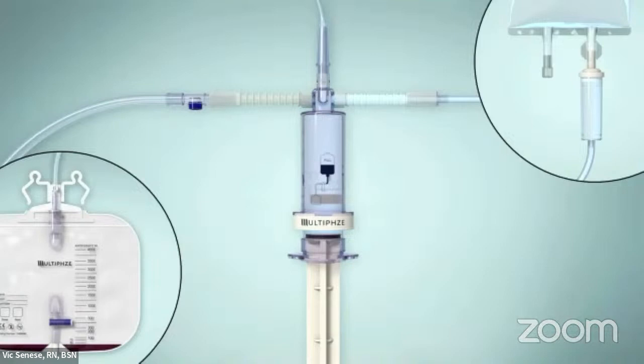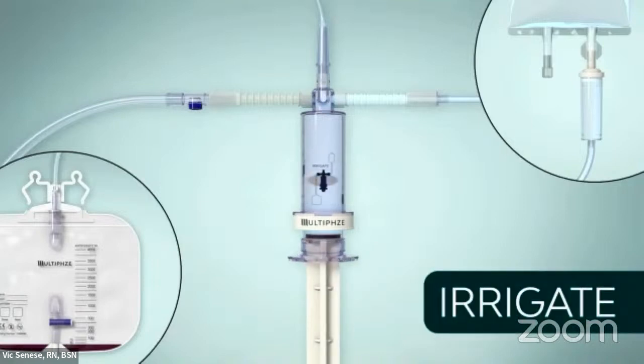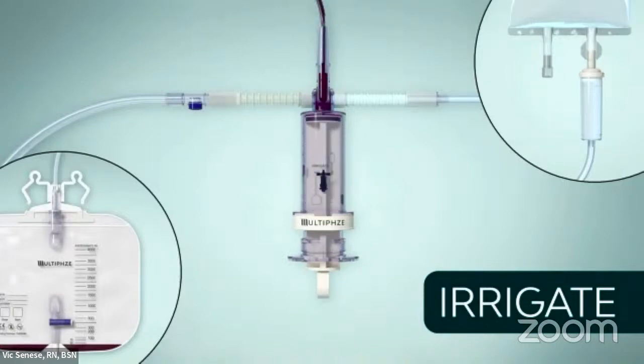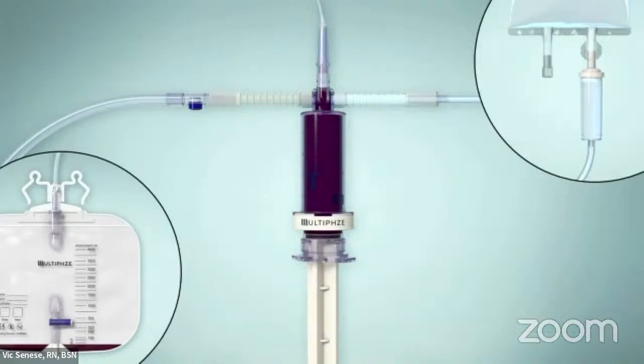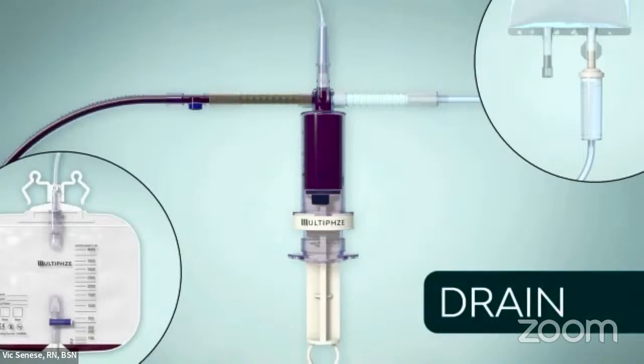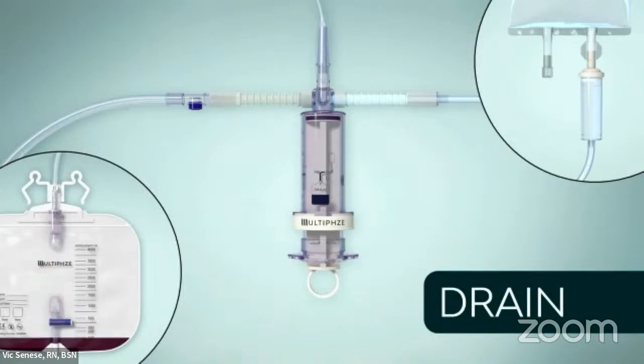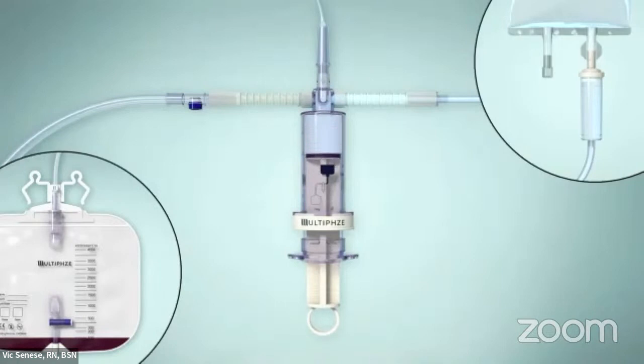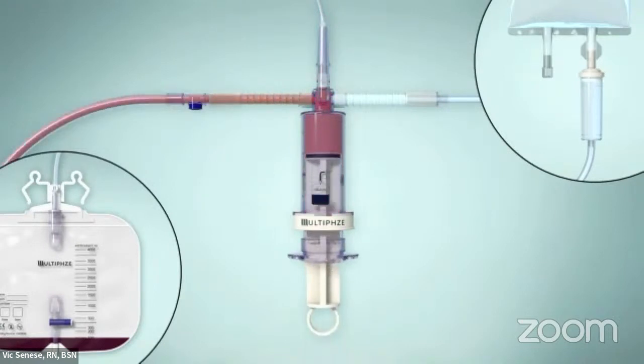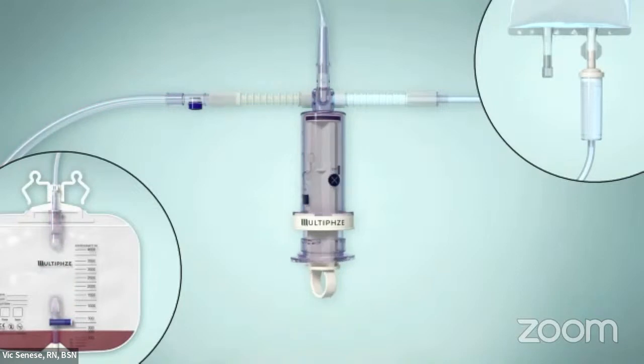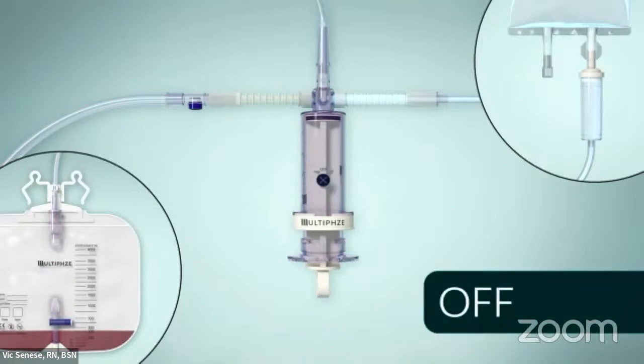With the syringe full of sterile solution, rotate it to the irrigate position. Then, push the plunger into the syringe to advance the sterile solution into the patient's bladder. Pull the plunger back to draw out the bladder contents into the syringe. Manually irrigate the bladder by pushing fluids back and forth through the syringe tip as needed. To clear the syringe, rotate it to the drain position. Then, push the plunger into the barrel and empty the syringe contents into the attached drainage bag. Repeat the fill, irrigate, drain steps as needed to complete the procedure. When the procedure is complete, rotate the syringe to the off position before disengaging the system from the patient's catheter.